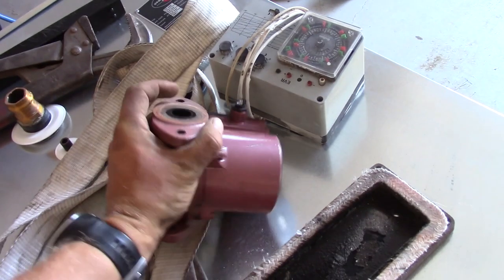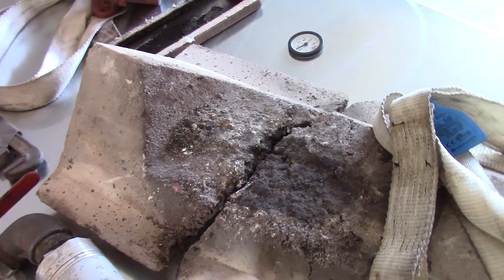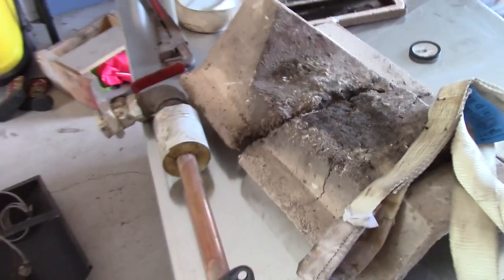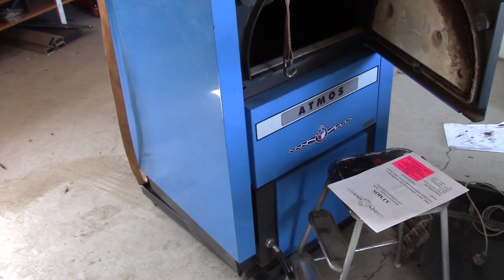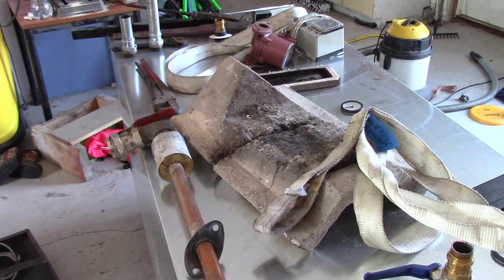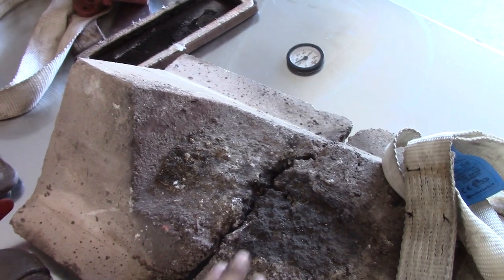Some pumps were included and of course a lot of pipes. This is the grate inside the boiler itself. As you can see, this one is pretty worn out, but that's the only thing I need to swap out. Note that this boiler is eight years old — they say those grates should hold up five to six years, but they used it for eight years and it's still fine, still workable.